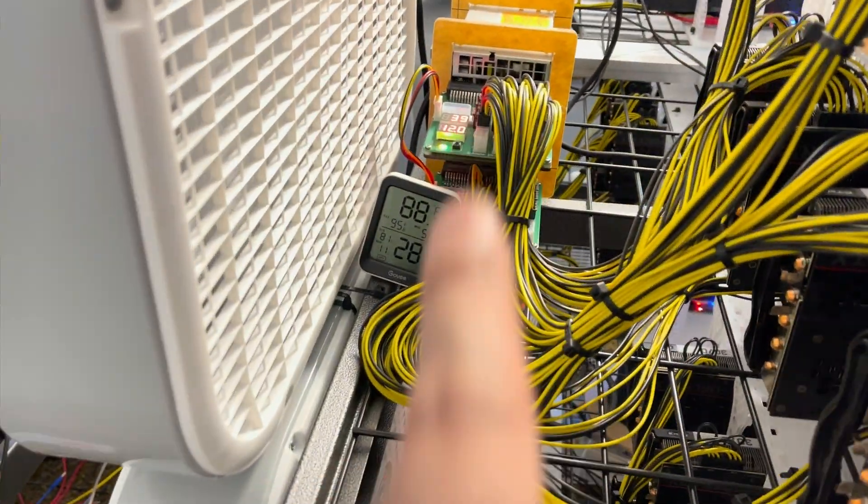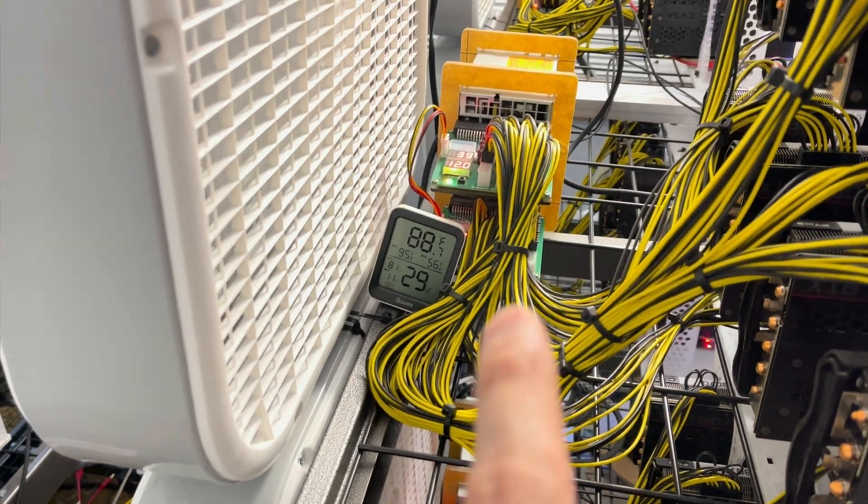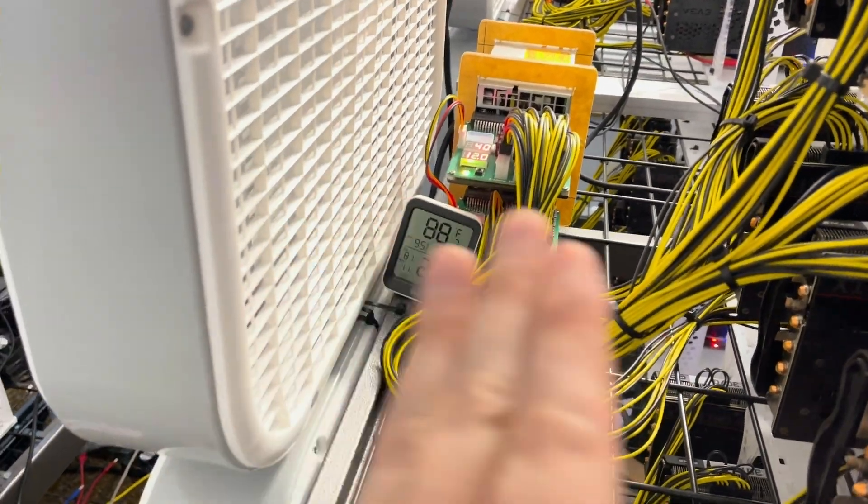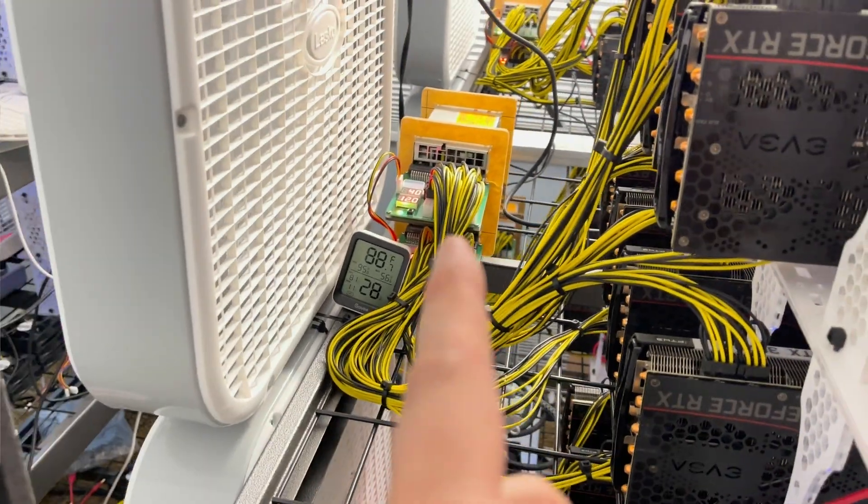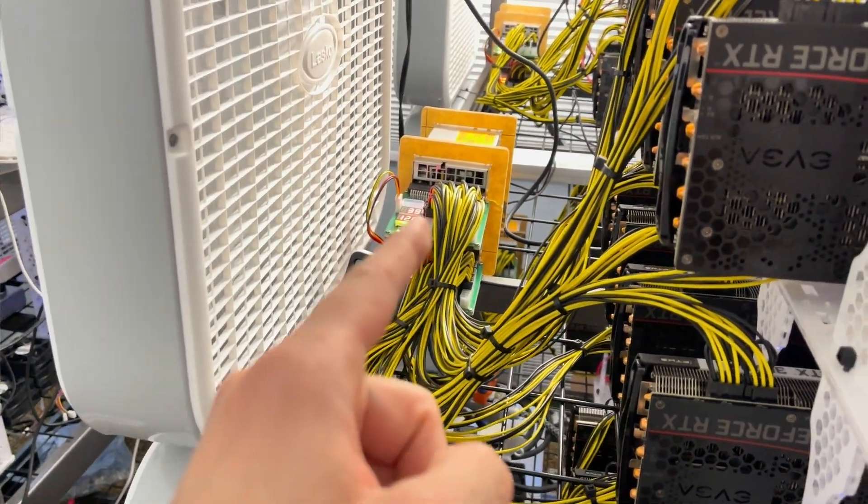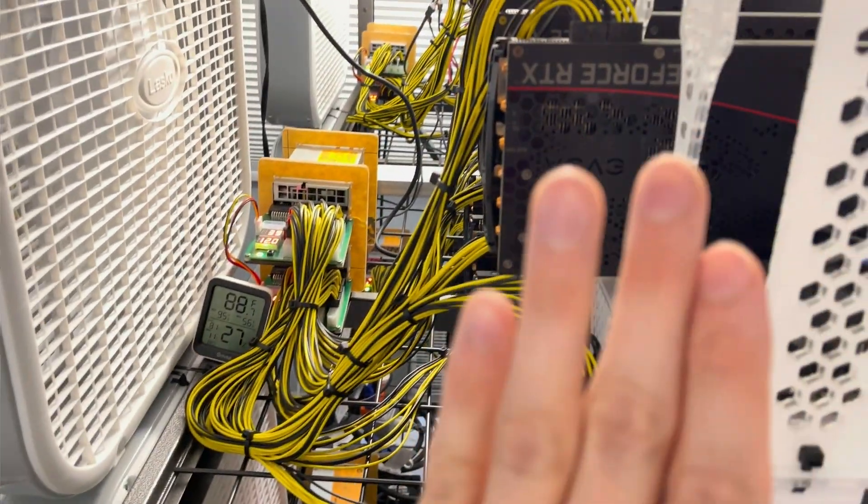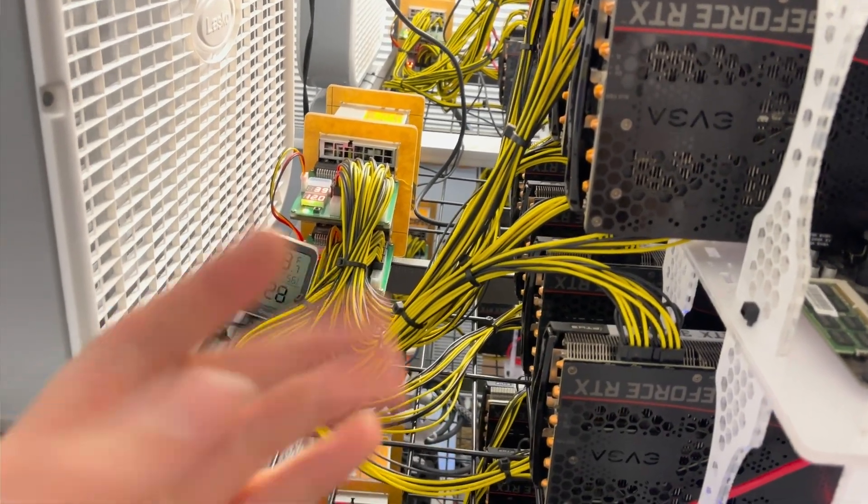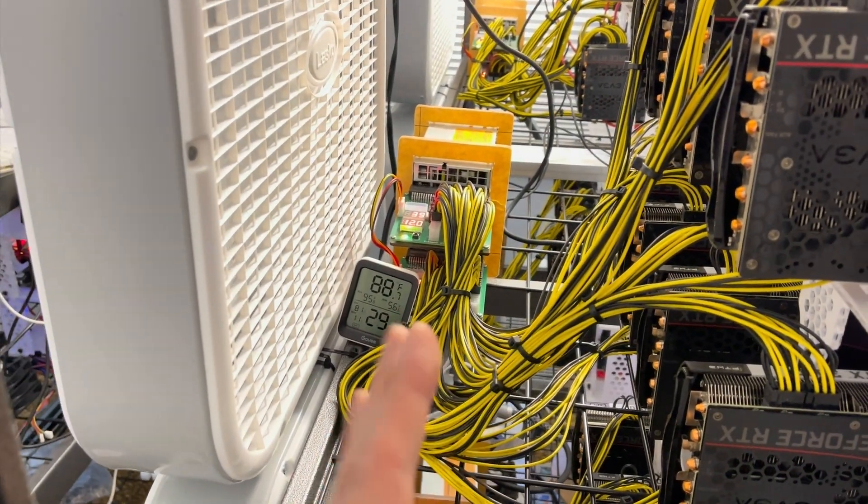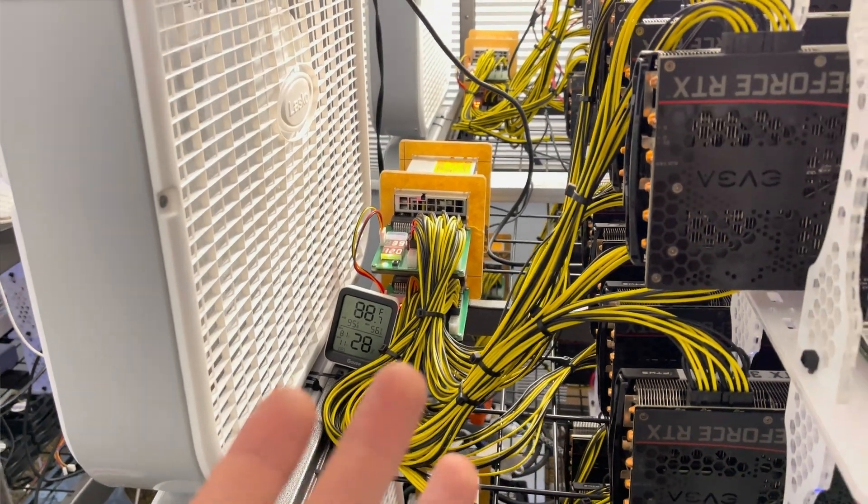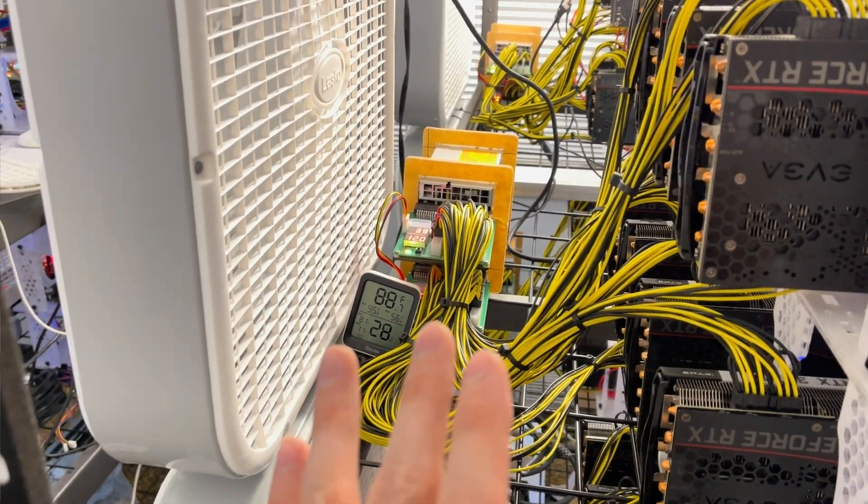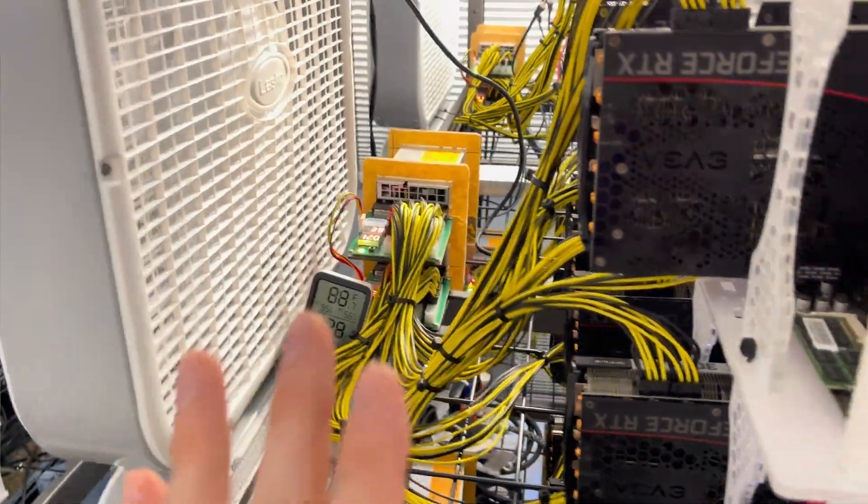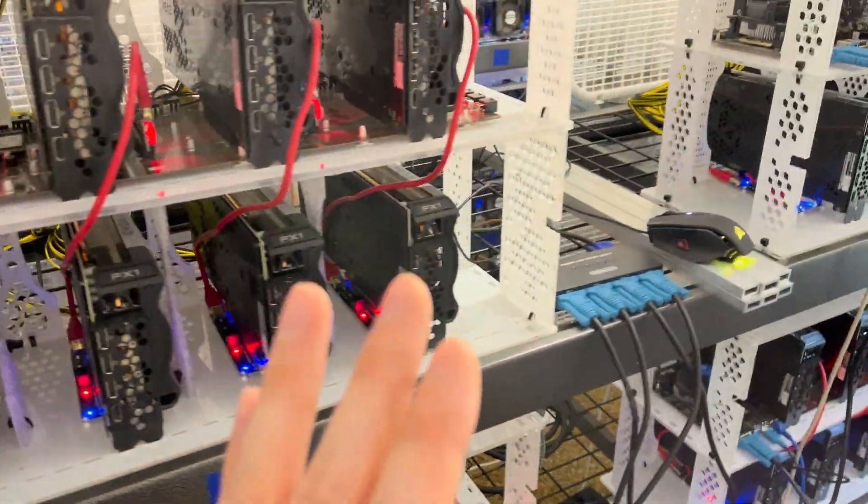So you really got to know your power supply to know how you should load it. But if you have an understanding like that, you could use that information to determine how much load to place on your power supplies. How many do I need? How many amps to put on each one? And you load your power supplies most efficiently. What that'll do is gives you the most amount of DC out that powers your cards for the least amount of AC in. This isn't a huge difference. It's somewhat minor, but in a lot of cases, it's pretty inexpensive to do. Depends on your setup. So if you could balance them better, maybe they'll save some power there.